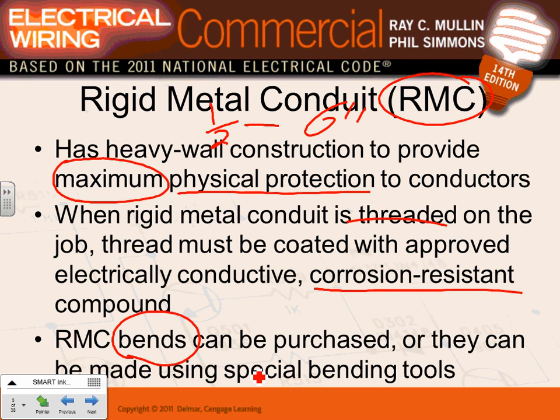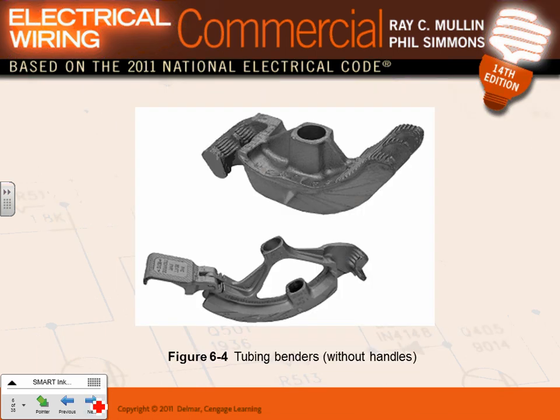Can you use rigid in a regular room? Yes. Is it a good idea? No. It's permitted almost anywhere - above ground, below ground, any location. You can hand-bend up to about three-quarter to one inch. After size one, you need hydraulic or electrical benders. Be aware that rigid takes longer for electricians to bend than EMT, which affects your estimating. That's why the conduit of choice for any building is EMT - unless you need rigid, you shouldn't use it.